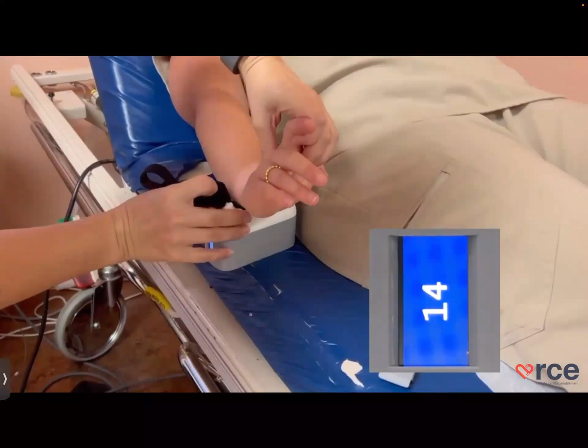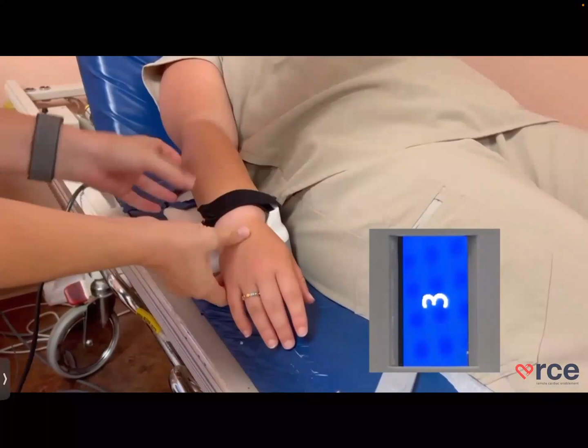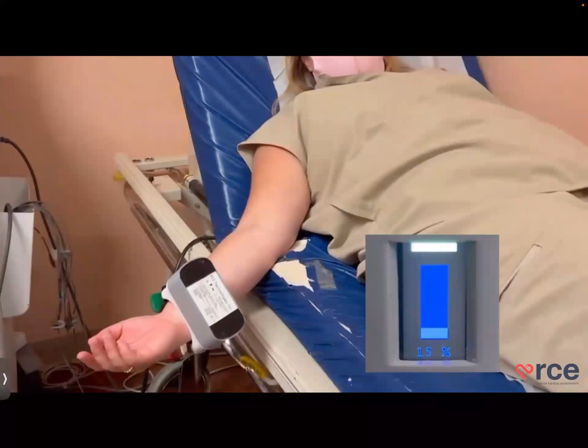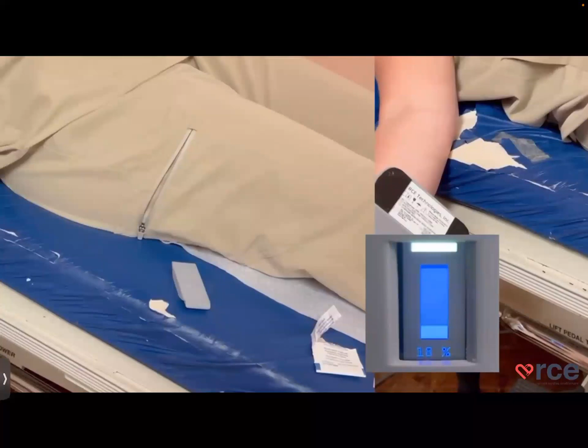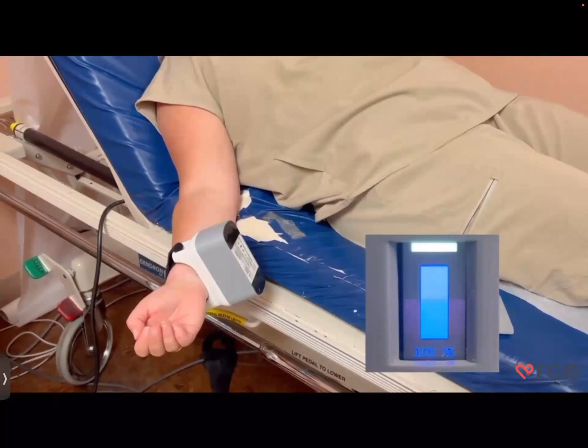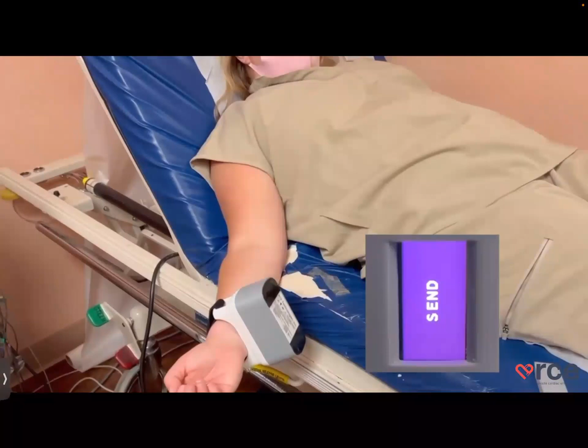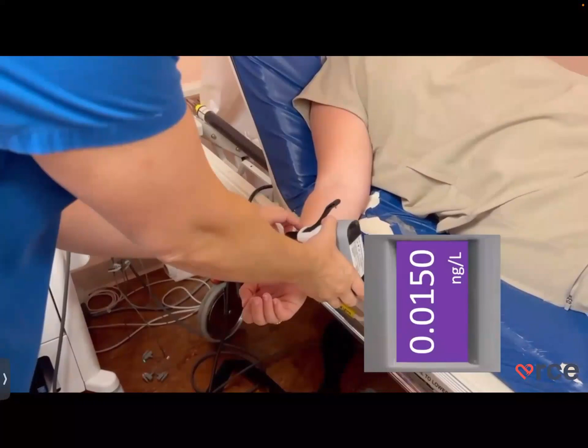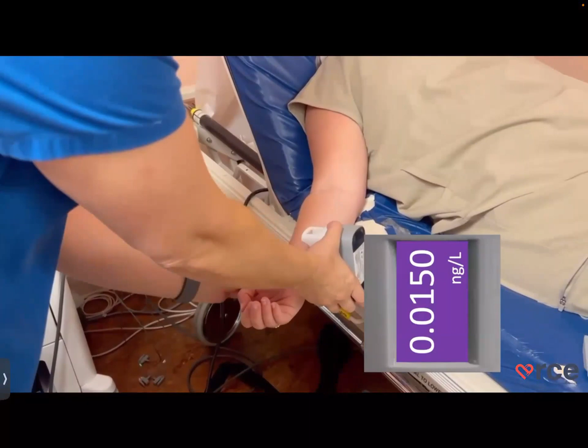Once the 45-second calibration is done, the device switches from calibration to an automatic patient acquisition phase. At this time, the clinical staff guides the patient's wrist onto the sensor surface, as you see here, and secures the patient's wrist onto the device with a wristband. You leave it on there for 3 minutes, and after 3 minutes, we're able to show the troponin concentration on the device. During these 3 minutes, we're acquiring an infrared spectral map. After 3 minutes, this data is collected and wirelessly sent to the cloud. In the cloud, the data is processed and immediately sent back to the device. So bedside, the patient, the staff, as well as the doctor can see the value of this troponin concentration.